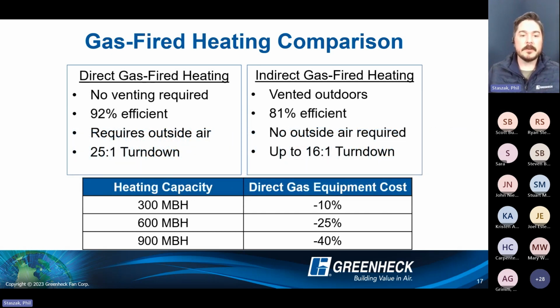Now, the biggest advantage on the direct gas fired side, though, is definitely upfront cost and then overall operating cost. Depending on capacity requirement, how much airflow you're moving, at 300 MBH and under, you're still looking at upfront costs typically 10% less for the direct gas fired equipment. And then as you increase that capacity requirement, you're going to see more of a gain on the direct gas fired side. Main reason being one single 6-inch burner section gives 400,000 BTUs of capacity. To get more heat, you just simply keep growing 6-inch burner sections.